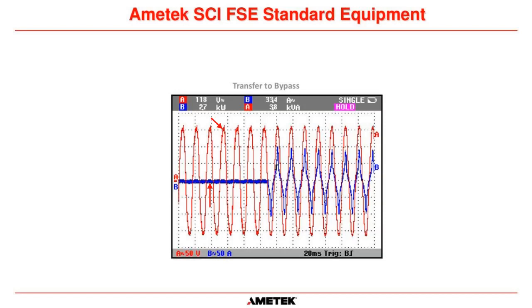Okay, so this portion of the waveform here is the output of the system before it was transferred to bypass, and this red waveform here is the output of the system after it was transferred to bypass. Because you can see at this point here, that is where our technician pressed the bypass to load push button on the front of the UPS, and the system transferred to bypass. How do we know that? Because current started flowing on the bypass cable. So we know that is the exact point that the system transferred from inverter to bypass. And as you can see with the red waveform, there are absolutely no chinks or dips in the voltage. That transfer took place without any issues whatsoever. So it's a very important reading that we take.